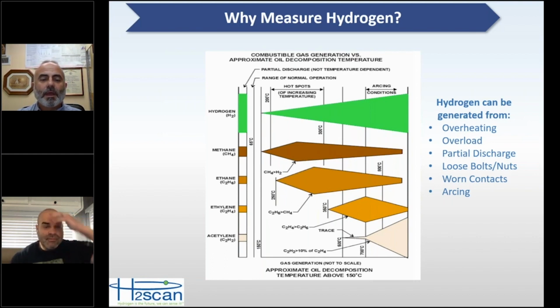once a year. And hydrogen is the gas that will escape from the transformer the fastest. It's the smallest molecule, so it will escape. If it's a very tight transformer, then it actually will stay in the oil. And if there's a nitrogen blanket, it will stay in the transformer a very long time. But especially as transformers age and they're not quite so tight and there's small leaks around gaskets and so forth, hydrogen will escape from the transformer.